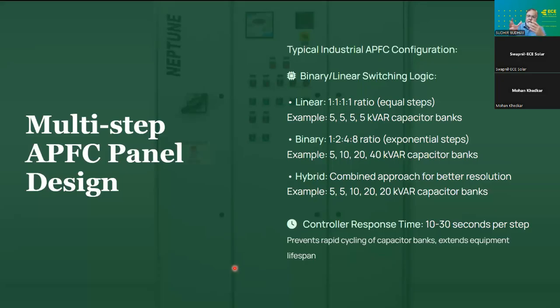So you use this, or you can go for hybrid where you need to program and tell the relay that stage 1 I am connecting 5 kVAR, stage 2 I am connecting 7 kVAR, like this. So you do programming, but there are certain smart hybrid relays also available today where they are smart enough to compute. When you get into programming mode, they will compute themselves. They will first discharge the capacitor. Then, based on the charging current, they will calculate and do self configuration automatically. And there are smart hybrid relays with 4 stages for single phase, each phase, and 4 or 8 stages for three-phase capacitors also.